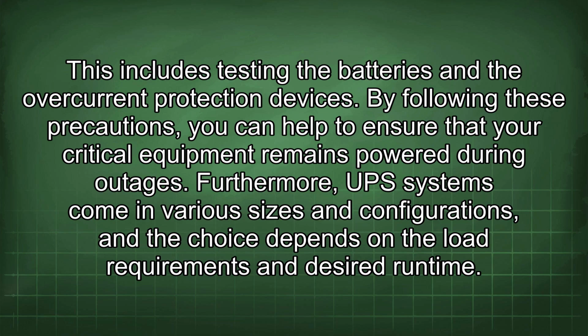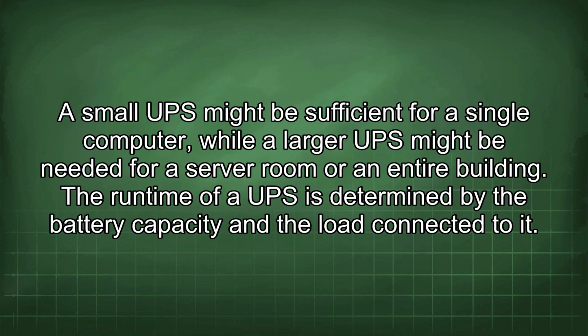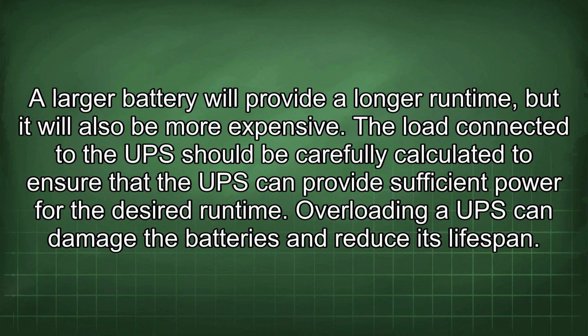Furthermore, UPS systems come in various sizes and configurations, and the choice depends on the load requirements and desired runtime. A small UPS might be sufficient for a single computer, while a larger UPS might be needed for a server room or an entire building. The runtime of a UPS is determined by the battery capacity and the load connected to it. A larger battery will provide a longer runtime, but it will also be more expensive. The load connected to the UPS should be carefully calculated to ensure that the UPS can provide sufficient power for the desired runtime. Overloading a UPS can damage the batteries and reduce its lifespan.